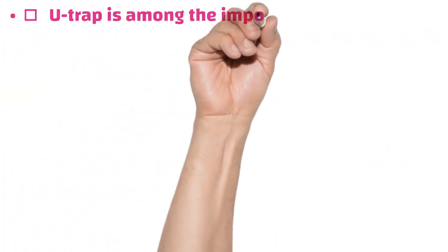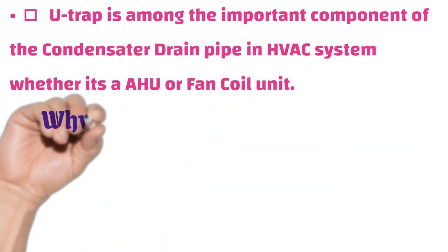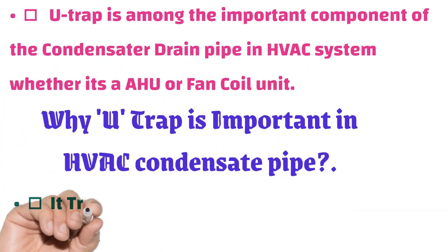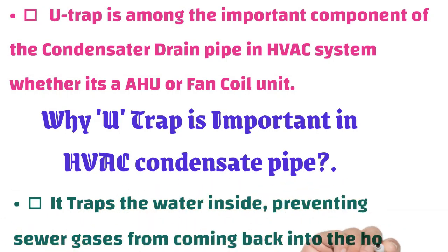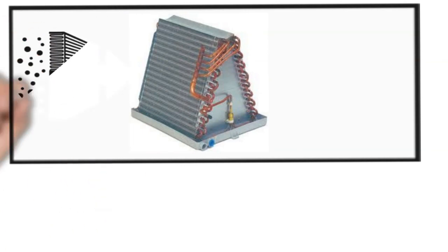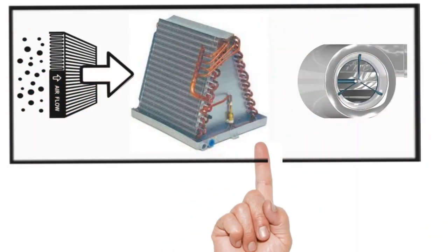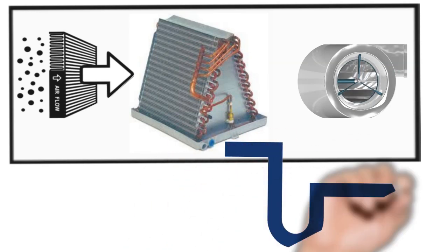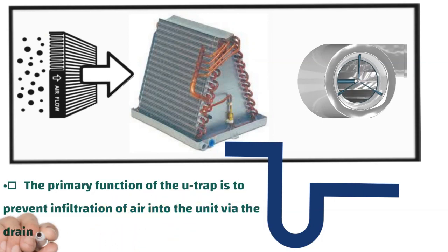The U-trap is among the important components of the condensate drain pipe in an HVAC system, whether it's an AHU or fan coil unit. It traps water inside, preventing sewer gases from coming back into the house. The primary function of the U-trap is to prevent infiltration of air into the unit via the drain line.